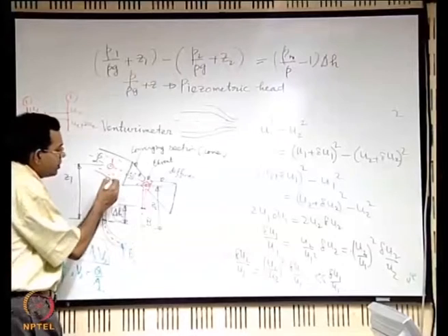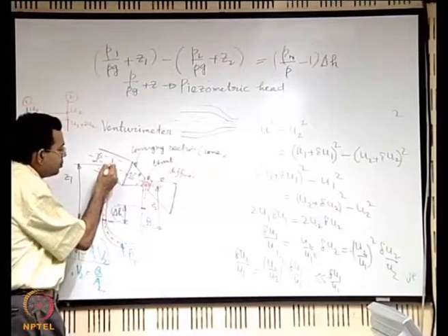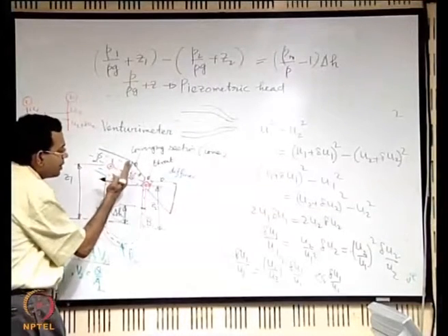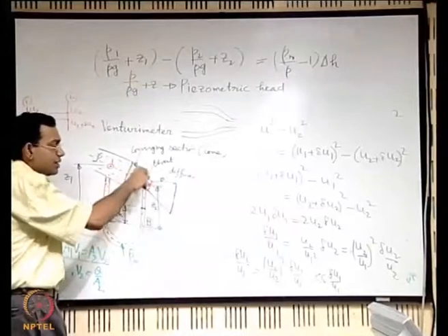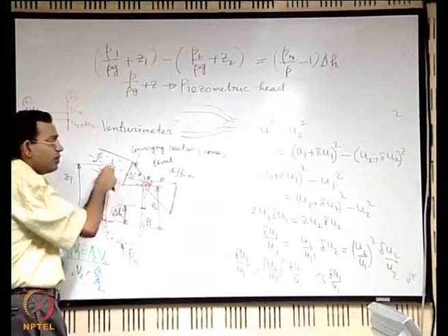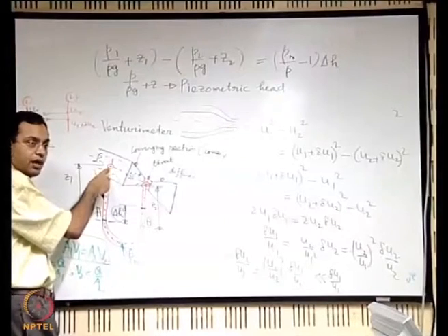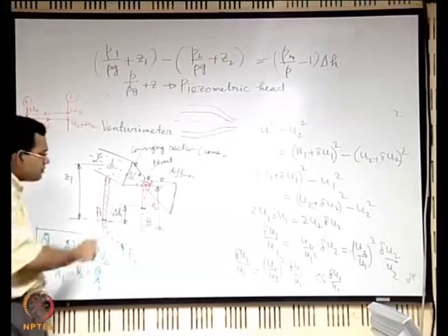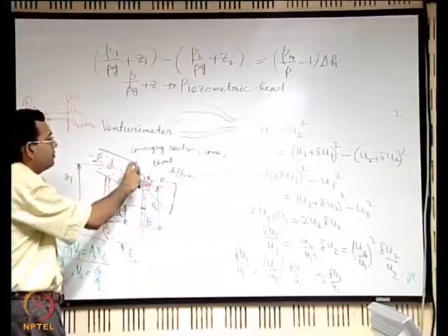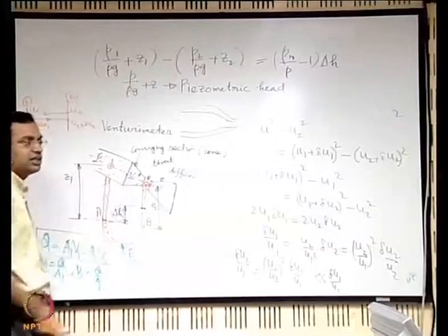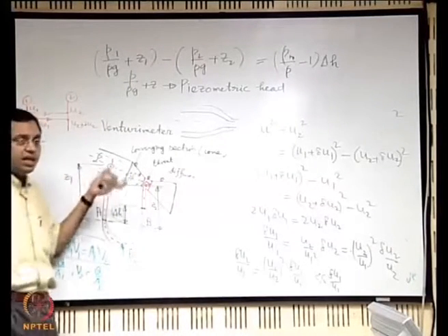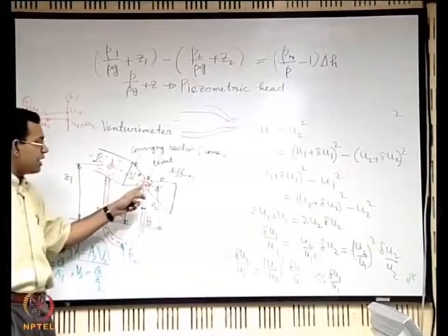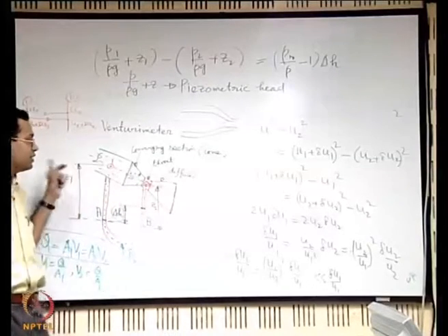One particular aspect on which one may not make a compromise is locating this section 1, where you have this manometer limb. It should preferably be somewhat away from the place where the reduction has started, so that the disturbance does not significantly influence the velocity at this point. Roughly, if the diameter of the pipe is d, it is a distance d away. Again it is a rough estimate; there are more accurate estimates for each device. So the connection of the pressure tappings is also very important, that is, where they are to be put.